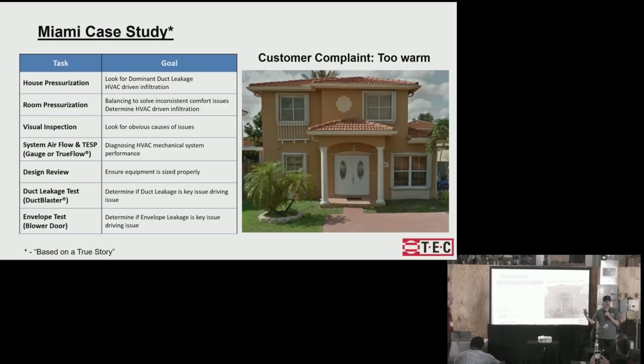The minute he got a gauge that said, I can walk into a house, and the first thing I do is house depressurization because I've got a gauge now that's accurate enough. You can do this with a blower door gauge from us or Retrotec. You can do it with a DG8 from us at a pretty low cost. But these super accurate gauges, you can walk into the house and within 2 minutes know, do I have a dominant duct leakage here? Is my house depressurizing when I turn on the HVAC system? If I do, man, that brings me a whole bunch of insight in 2 minutes.